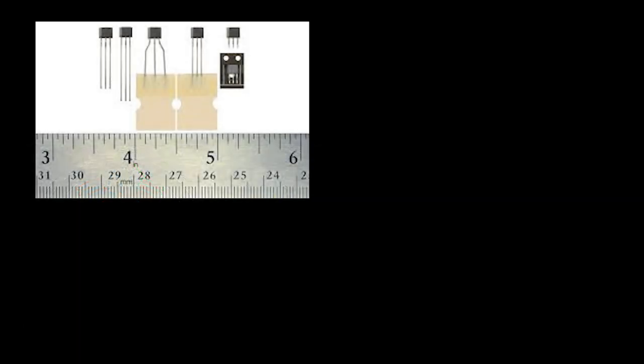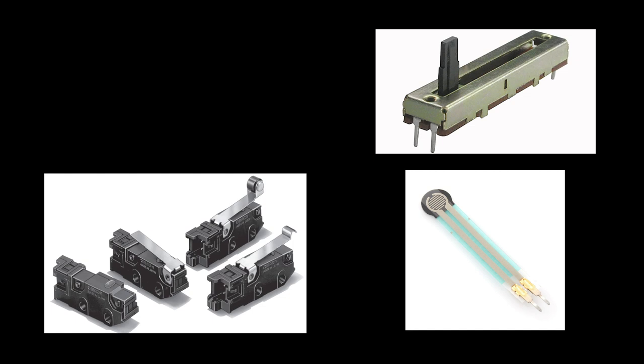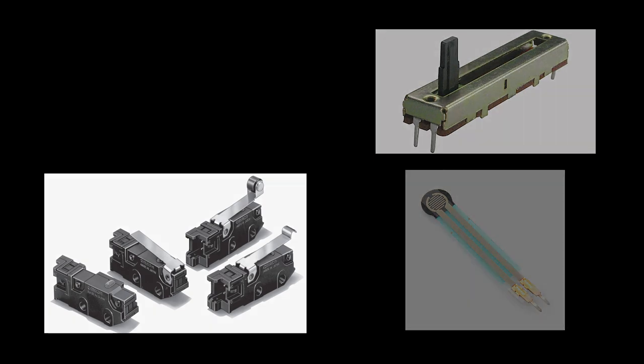Hall effect sensors are becoming much more prominent in medical equipment because the sensors themselves can be neatly contained within a device and free from exposure to harsh cleaning agents or physical damage. Using Hall effect sensors for detecting instead of micro-switches or variable resistors eliminates a mechanical component which is traditionally a high point of failure in a device.